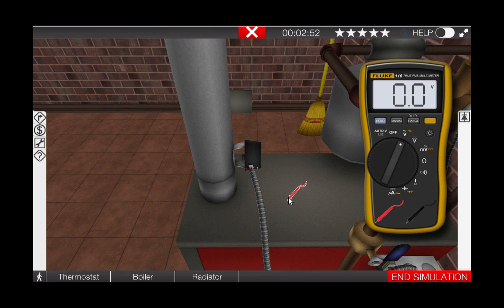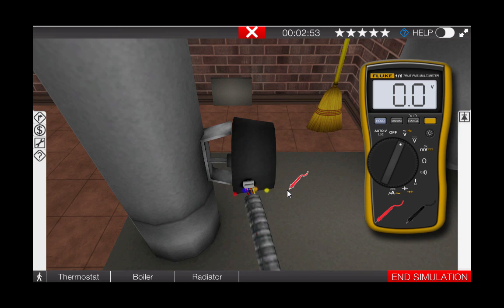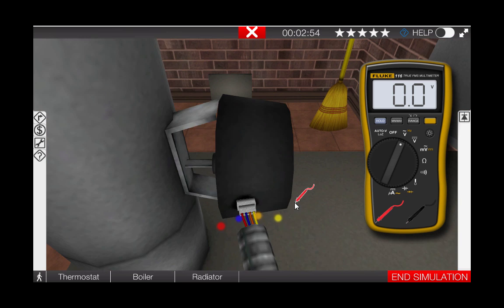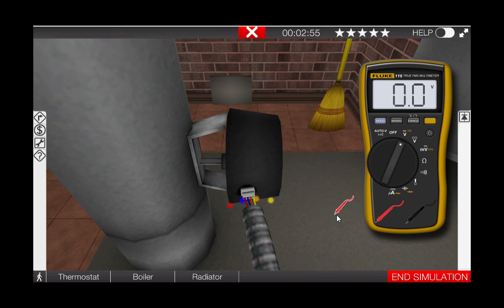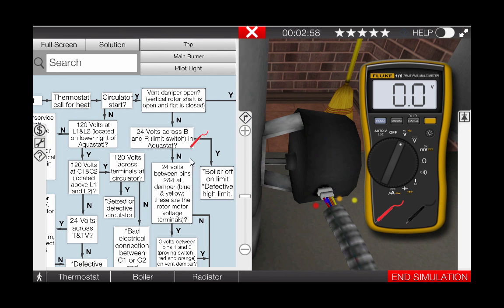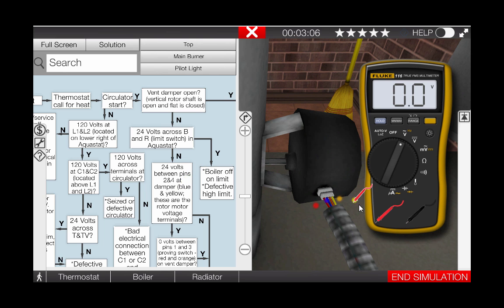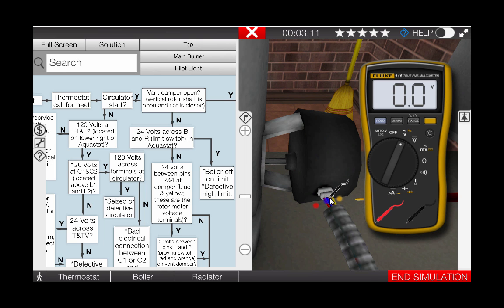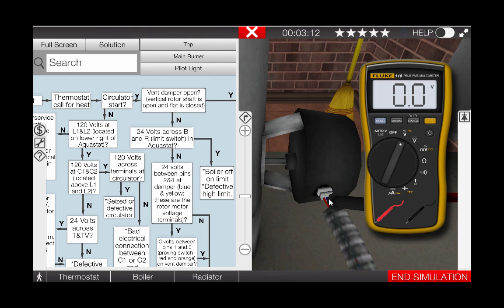Again referring back to the troubleshooting flowchart, we can see that the motor connections are between pins 2 and 4, or the blue and yellow connection wires at the vent damper motor. Place each of the meter leads across the blue and yellow glowing hot spots at the vent damper motor.